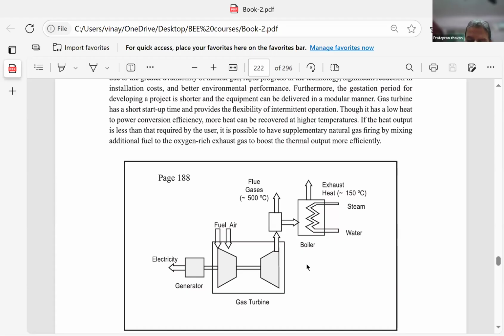But the peculiarity here is that the gas temperature at the exhaust is in the range of 500 plus. Many gas turbines exhaust at 650 or 700 degrees centigrade. In steam turbines, we have seen the major loss point is the condenser, where the steam gives out its heat to the cooling water.